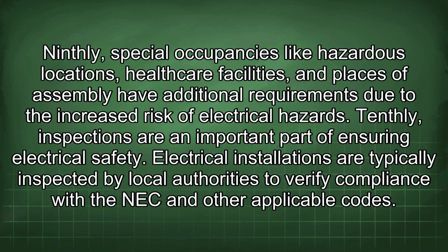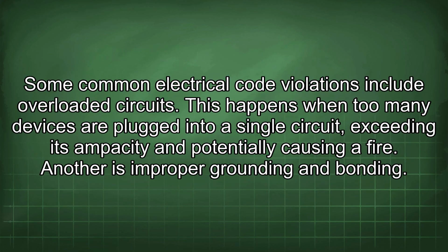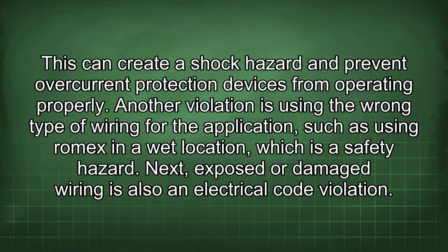Electrical installations are typically inspected by local authorities to verify compliance with the NEC and other applicable codes. Some common electrical code violations include overloaded circuits. This happens when too many devices are plugged into a single circuit, exceeding its ampacity and potentially causing a fire. Another is improper grounding and bonding. This can create a shock hazard and prevent overcurrent protection devices from operating properly.